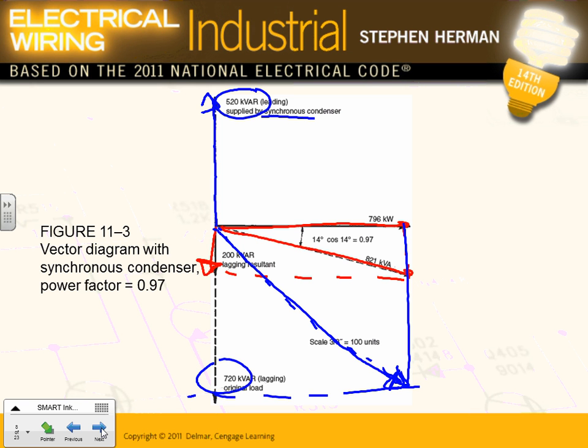If one of them is bigger than the other, it's going to push you in that direction, equivalent to the difference between them. So the kVAR left in my system is 200. Here's my kW, and my new kVA system, Jeff, my friend, is 821 kVA. My new kVA system is 821 kVA. So I was able to reduce it from almost 1,000 to 821 kVA. Any comments, guys? Any questions? I will go over the calculation in detail tomorrow, like I said.